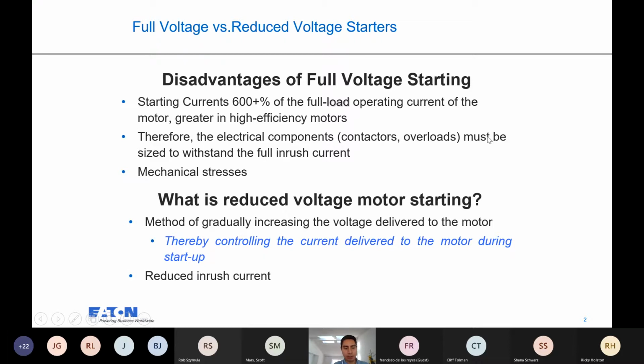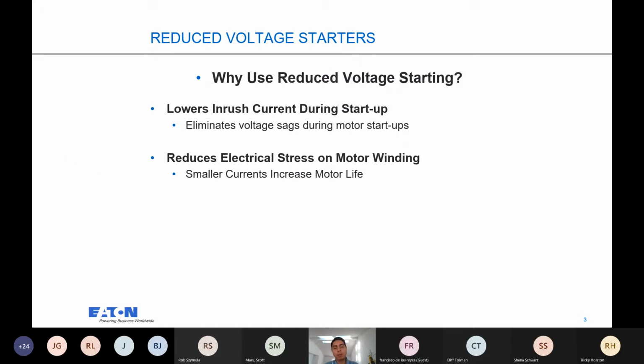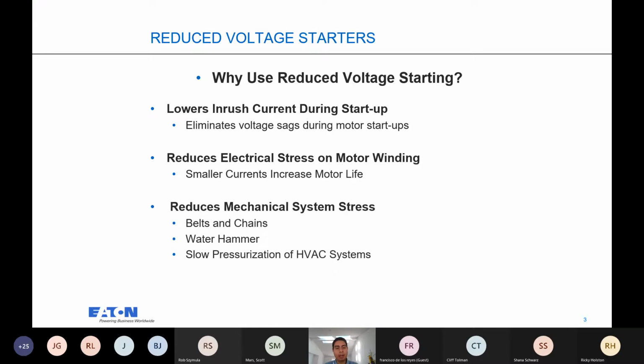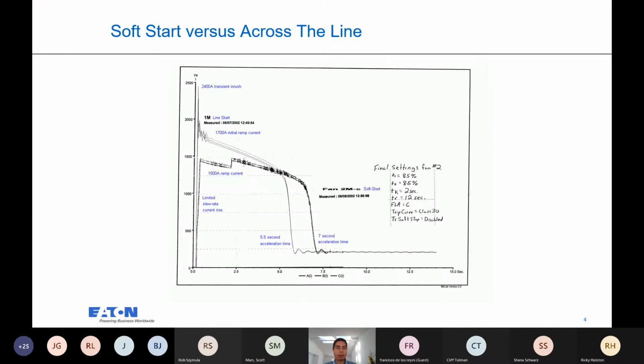Reduced voltage starting will be shown in a second here, and I do have noise here on the slide, so hopefully I can mitigate that at some point. So for the reduced voltage starters, why would we reduce the voltage? Again, as I mentioned, to reduce electrical stresses and mechanical stresses and increase the motor life. And I really want to go to the graph here. Across the line creates a 2,400 inrush initially, and once we go into reduced voltage starting, we can see that it is heavily reduced to 1,500.